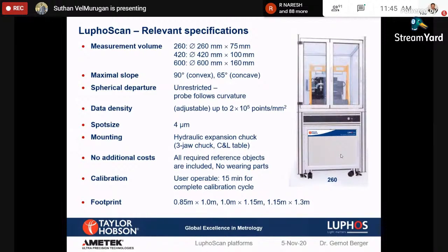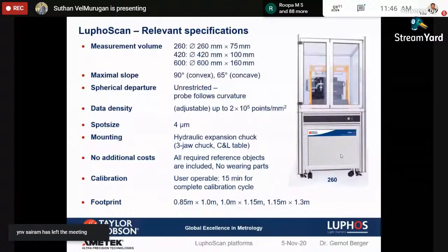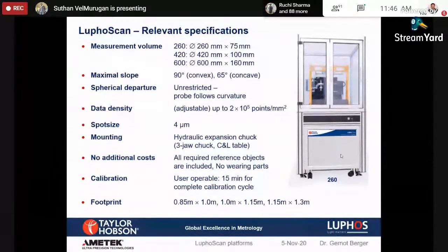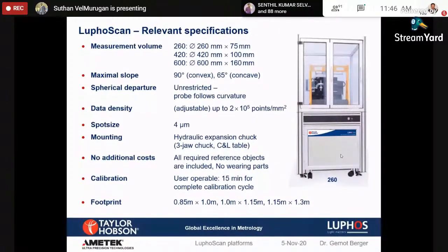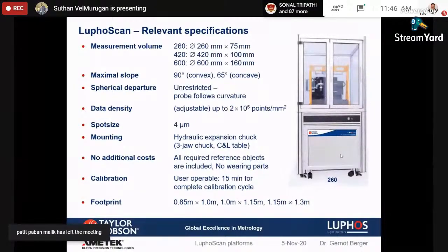It's only one line. So if you are trying to cover the entire 3D surface, it is going to take more time, probably 15-20 minutes. But in the non-contact, there is nothing that is going to touch, so we have no limitation of the speed. Unless we get very good data from the machine, we can rotate at any speed. If it rotates 100 RPM, like a 100 millimeter diameter part, probably we can measure it within 2 to 3 minutes for the entire surface finish. That is the major difference and major advantage of non-contact against the contact profiler.